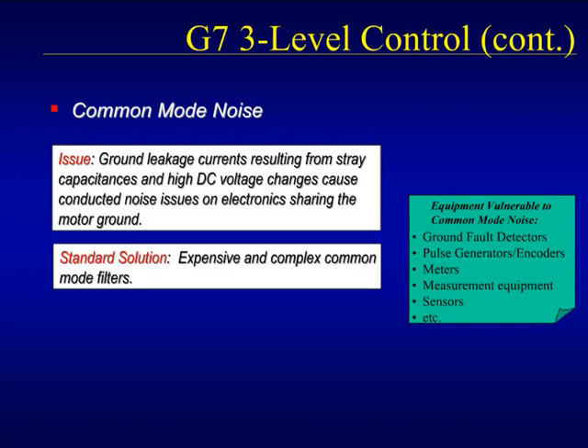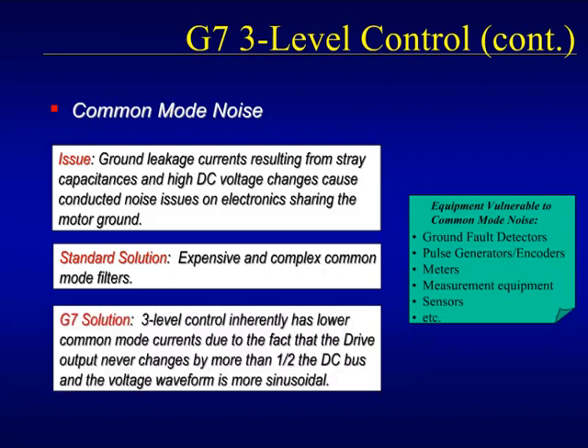Again, solutions to this point have involved money spent on expensive and complicated external equipment like common mode filters. Because of the way that 3-level control reduces dVdt effects by stepping the output voltage, the common mode noise at the drive output is reduced to levels below that of 2-level drives and may not require external equipment.